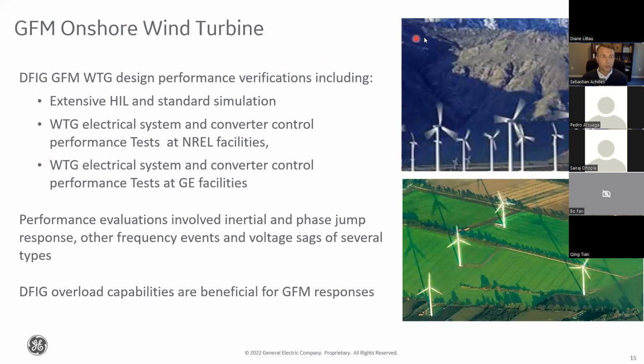The evaluations of performance cover a number of things. Maybe of particular relevance is the inertial response and response to phase jump. That was a key aspect of grid forming, and we tested that in all of those ways. We also looked at other frequency events like sustained frequency excursions. And then we also looked at voltage sags and fault behavior of balanced and unbalanced types. This was helpful to fine-tune the controls, and we were able to get performances that support this idea of operating systems with a lower number of synchronous machines in the system.